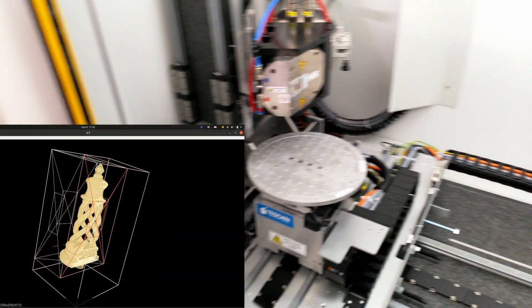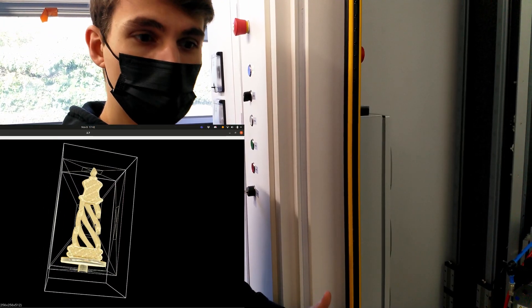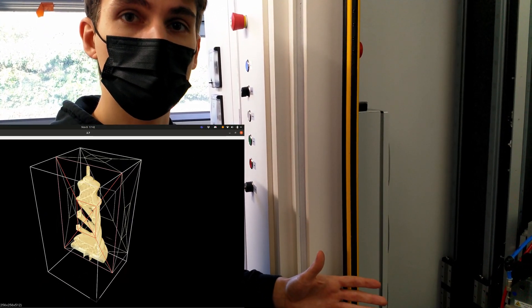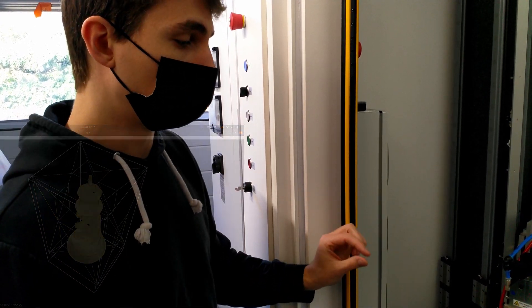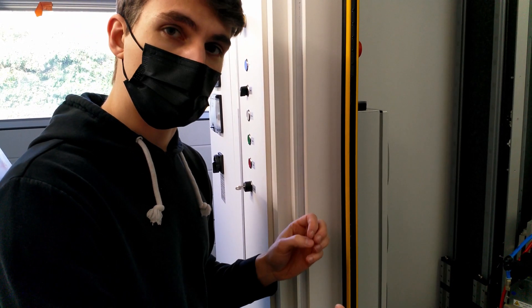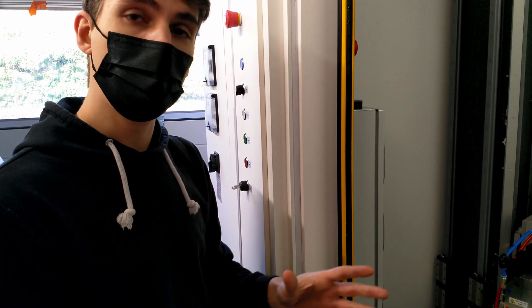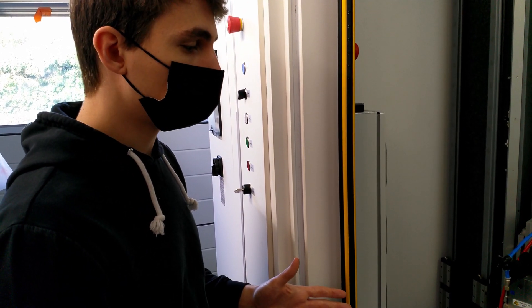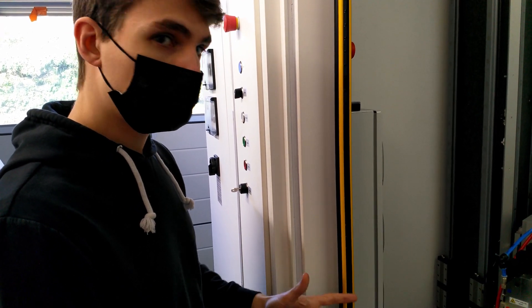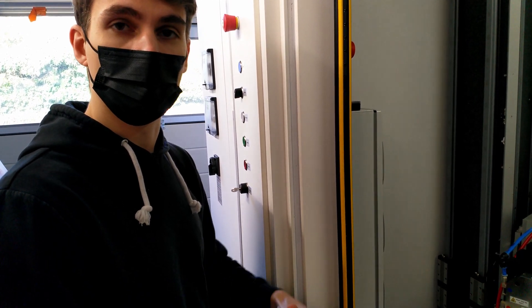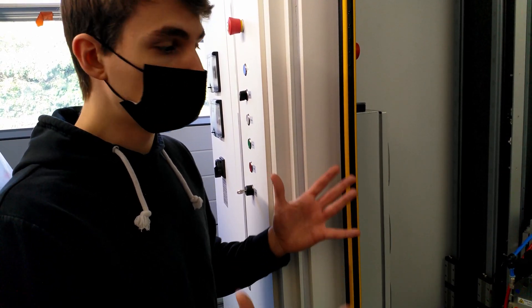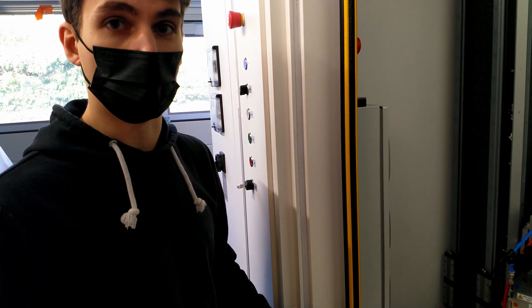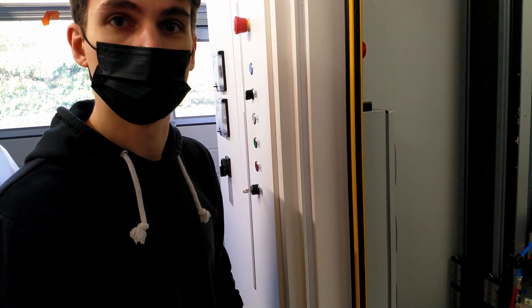We use mathematical algorithms to reconstruct a 3D image. A 3D image is made up out of billions of voxels with unknown intensities, unknown gray values, and each projection gives us many linear equations about these unknown intensities. So to find the unknown 3D image, we just have to solve a huge system of linear equations with billions of unknowns, which modern computers are good at with modern mathematics.